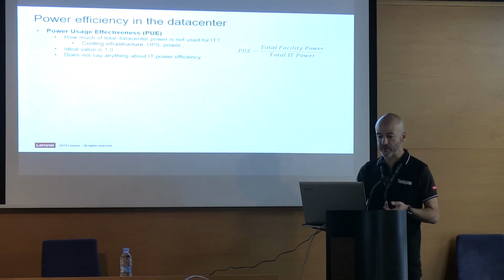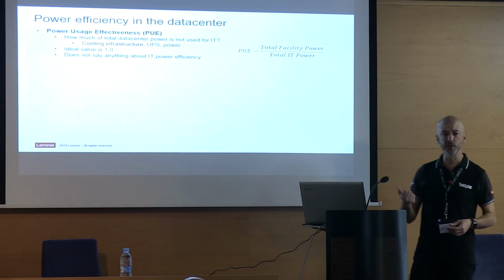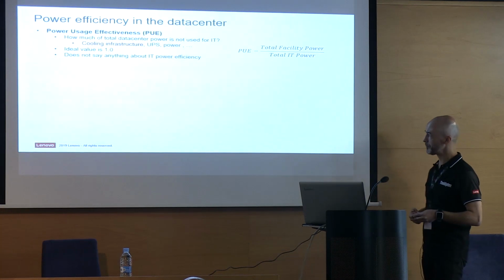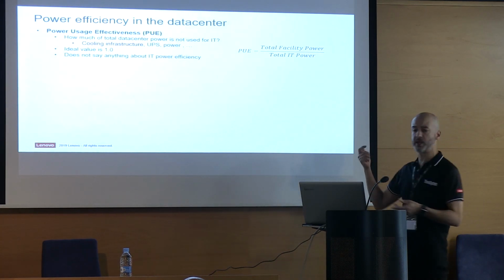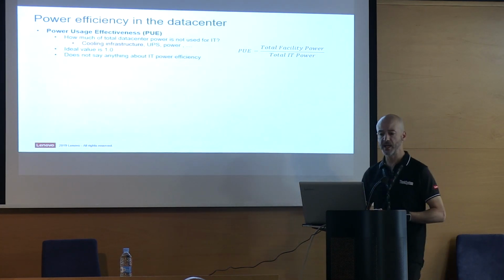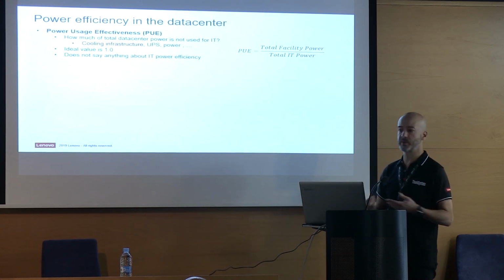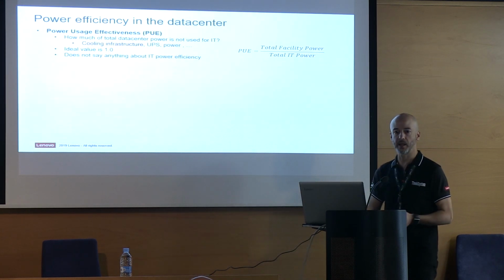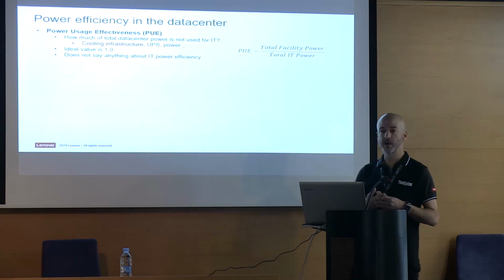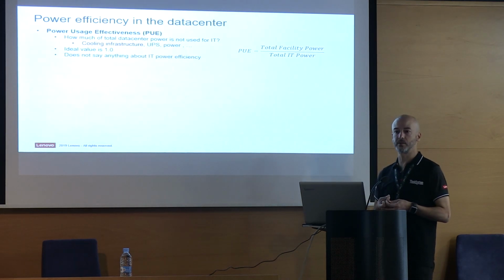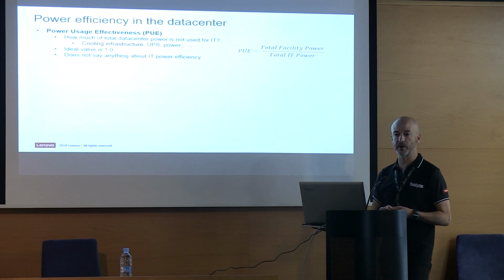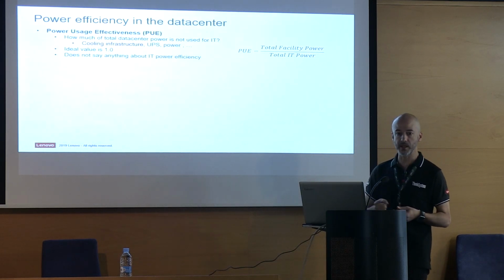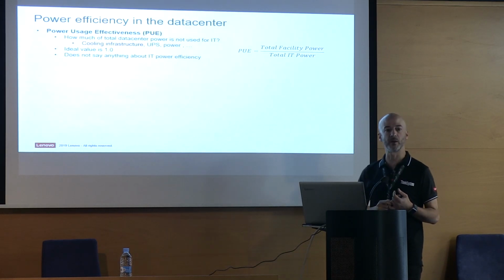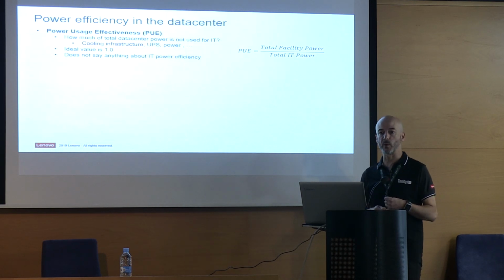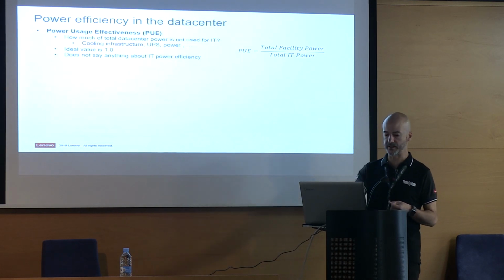So regarding power efficiency, we're used to dealing with this number, the power usage effectiveness, the PUE. Traditionally, we know what it is: the relation between what we spend in power versus the real power we can use for our IT equipment, including the cooling infrastructure, meaning all the chillers and CRAHs we use for our data center.